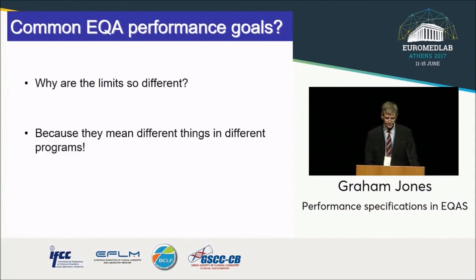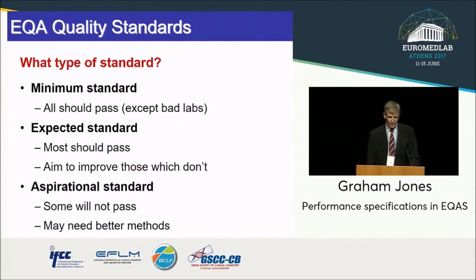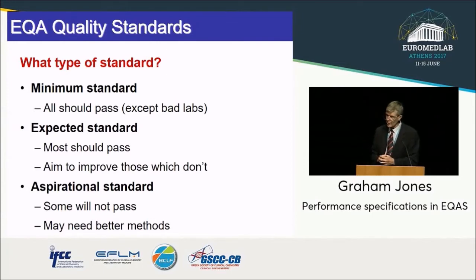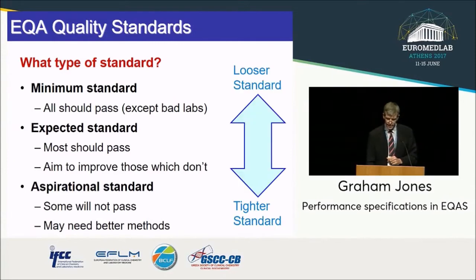Why is this variability? It's because they mean different things. EQA quality standards can be set for different reasons and they have different effects. The EQA organiser might have set a minimum standard — wanting everyone except the really bad labs to pass. At the other end, you might have an aspirational standard that drives improvement toward the best possible goal. And depending on the philosophy adopted, you might have wide standards or tight ones. For those affecting registration, like CLIA in the United States or RiliBÄK in Germany, being outside has regulatory implications, so they tend to be wider.